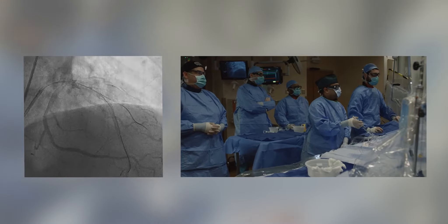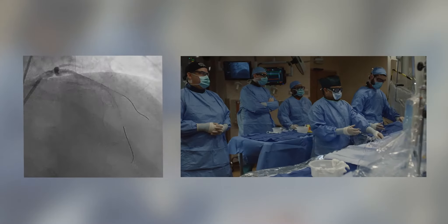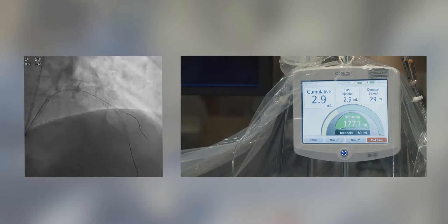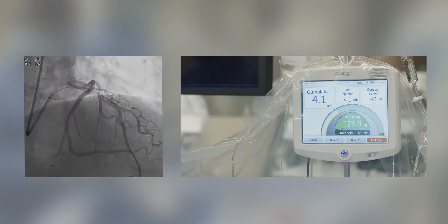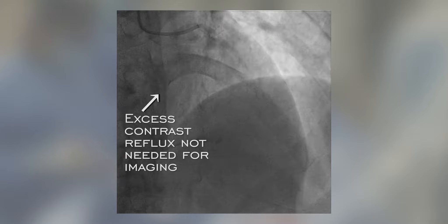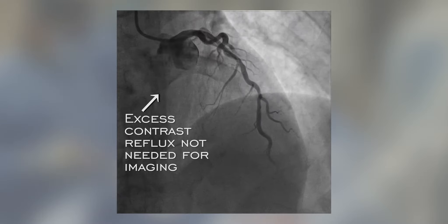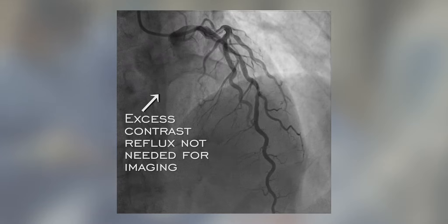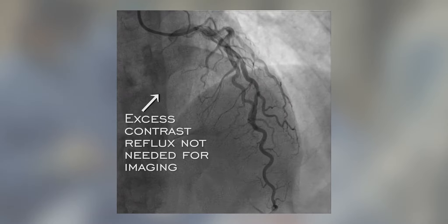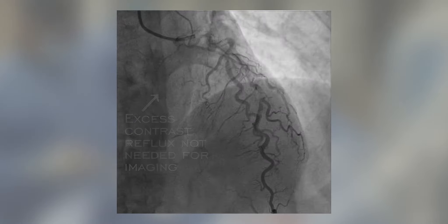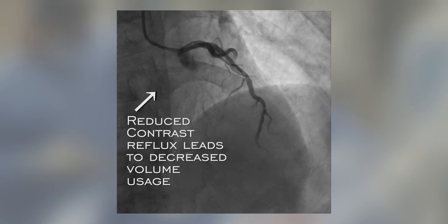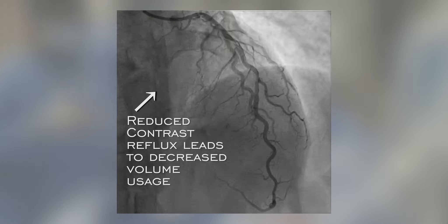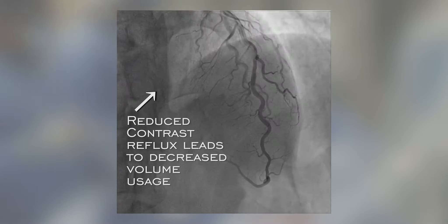The Divert System reduces contrast dye dosage injected into the patient by 40% on average without compromising fluoroscopic image quality. During a typical injection into the coronary arteries of the heart, excess contrast is refluxed into the aorta. Excessive reflux is not needed for imaging, and Divert reduces contrast reflux, resulting in decreased contrast volume usage without compromising image quality.